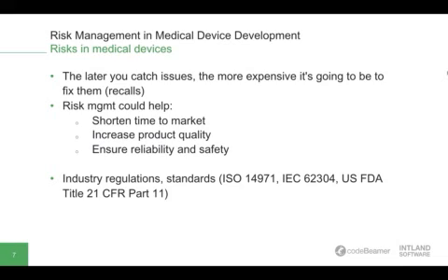And according to data from the US Food and Drug Administration, software failures were responsible for 24% of medical device recalls in 2011. Now, that's a huge portion of recalls, and this leads us to our next topic of why risk management is important in medical device development.